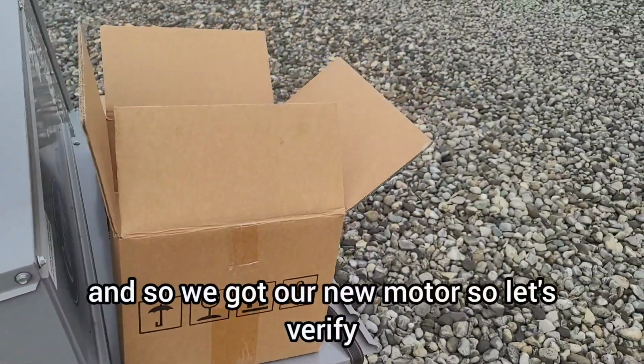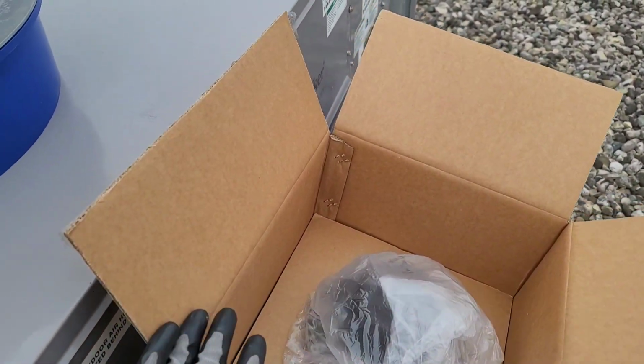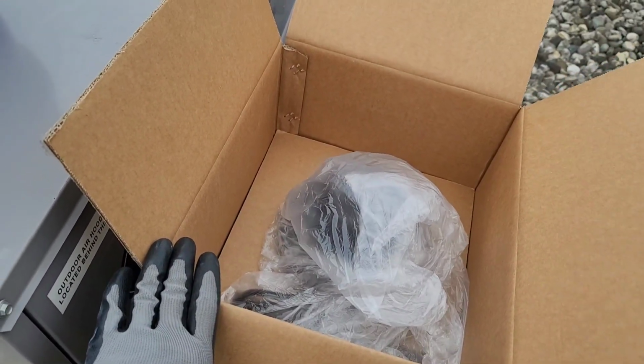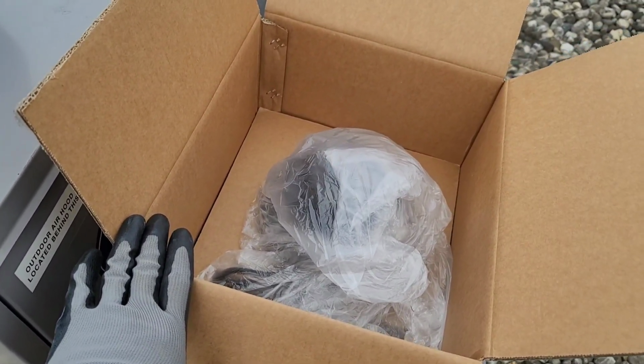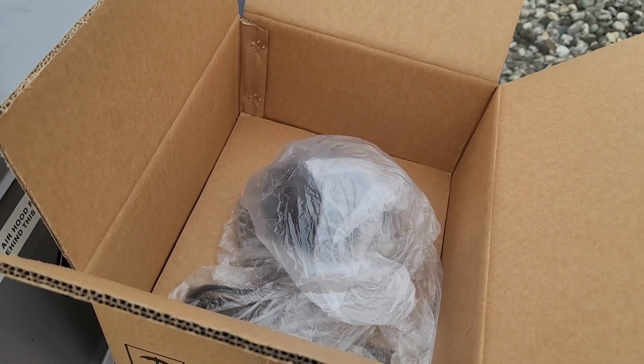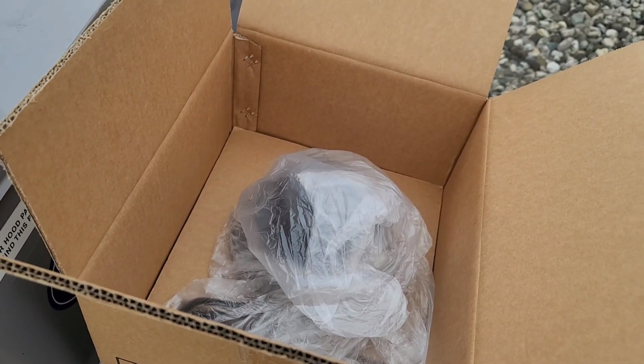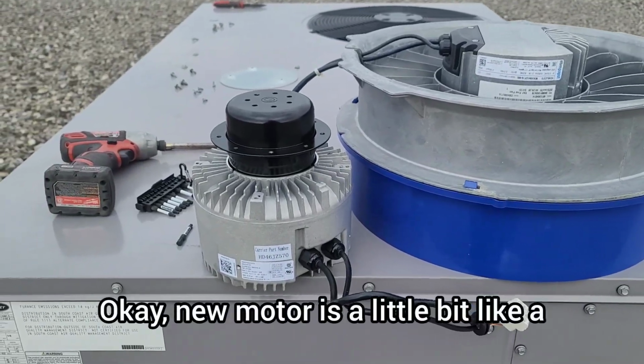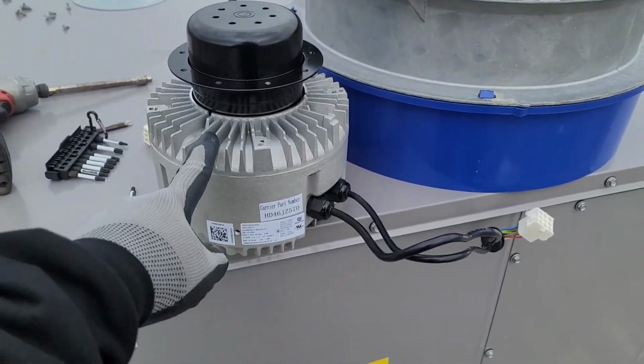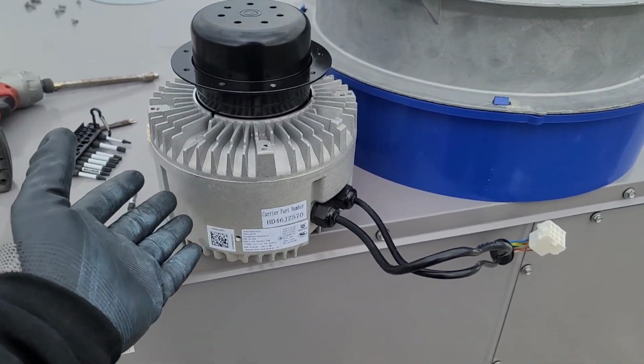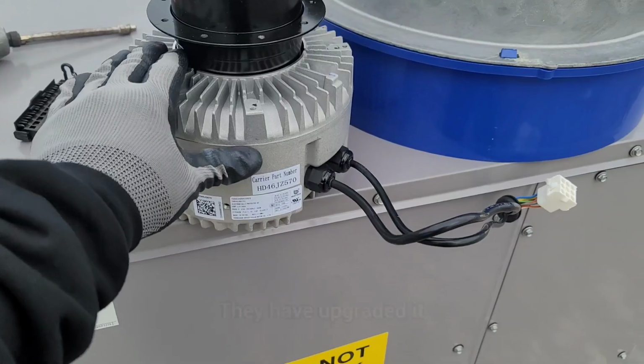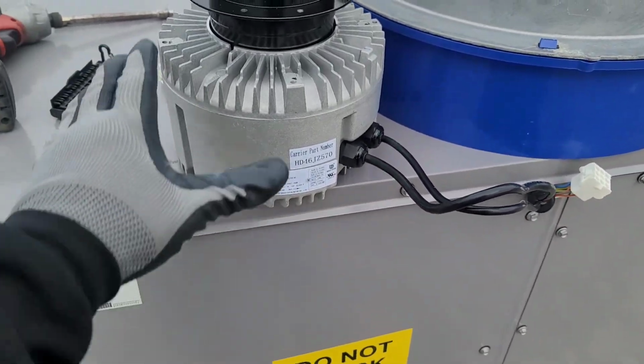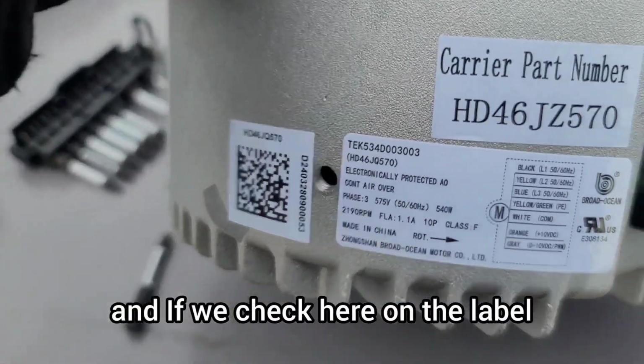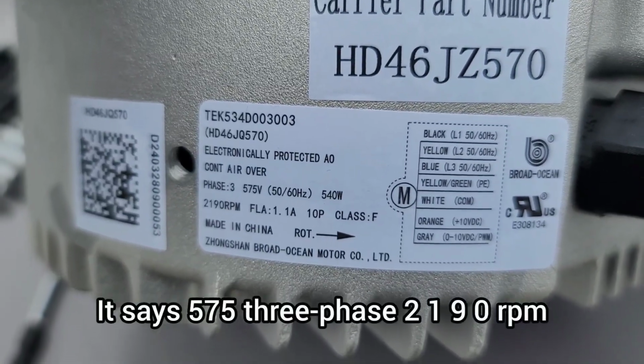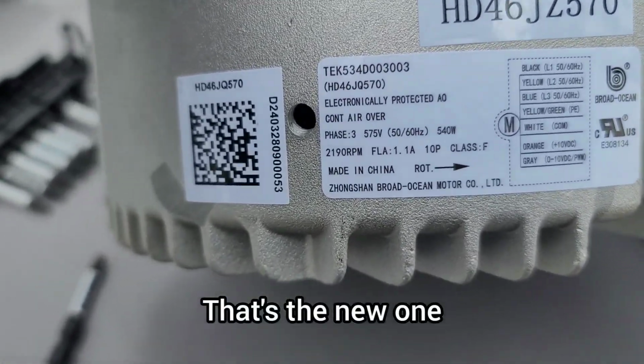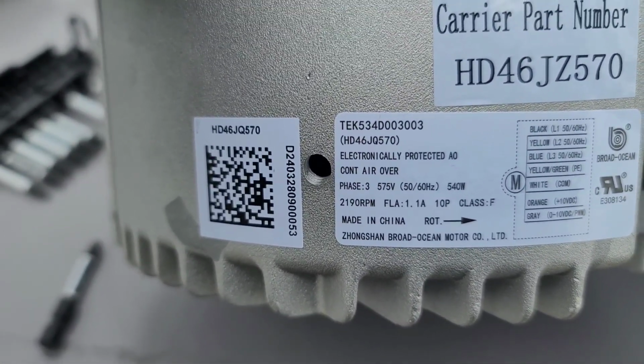And so we got our new motor, so let's verify the electrical spec with the older motor. Okay, the new motor from the outside is a little bit different, even the part number is different. They have upgraded it. And if we check here on the label, it says 575, 3-phase, and 2190 RPM.